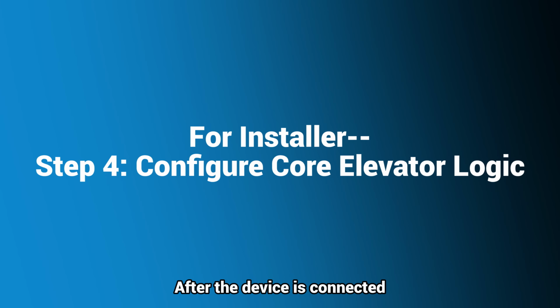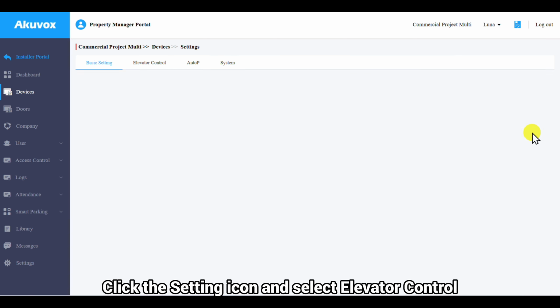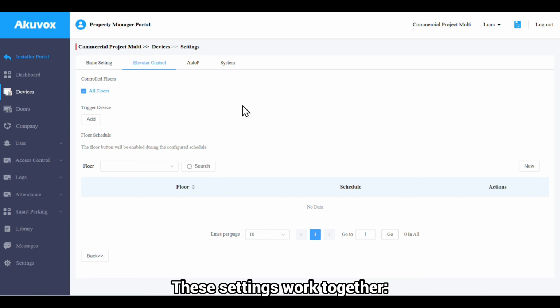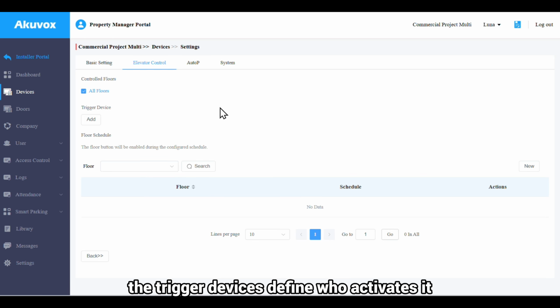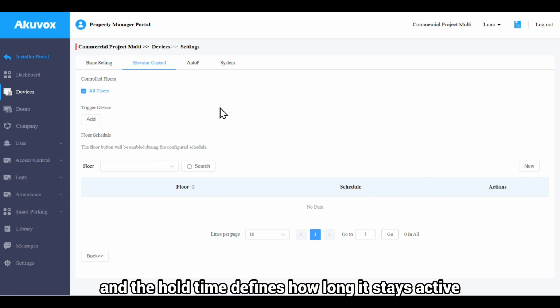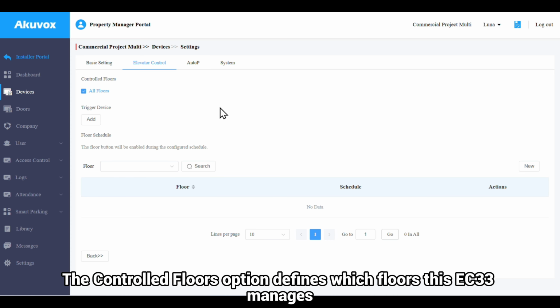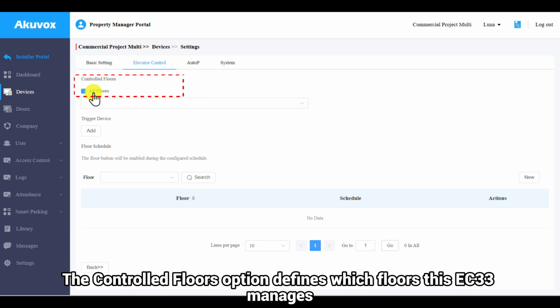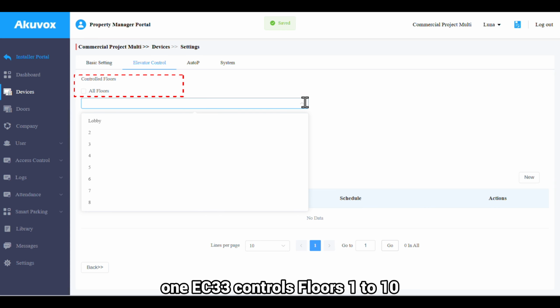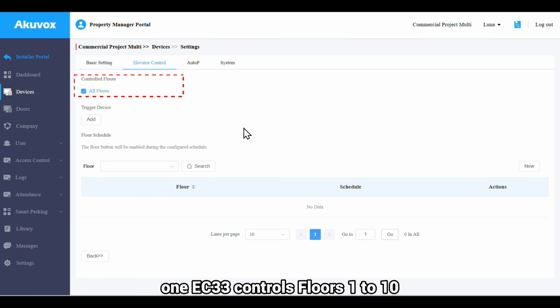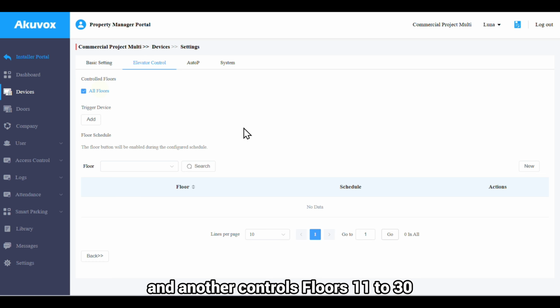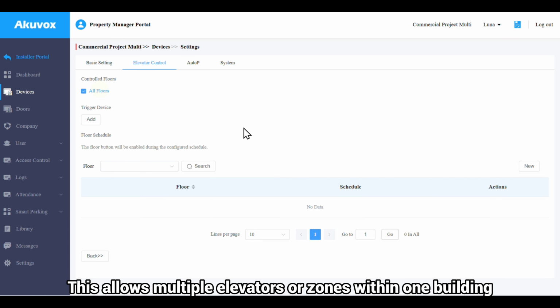After the device is connected, we can define how it behaves. Click the setting icon and select Elevator Control. These settings work together. The floors define the scope, the trigger devices define who activates it, and the hold time defines how long it stays active. The Controlled Floors option defines which floors this EC33 manages. For example, one EC33 controls floors 1 to 10, and another controls floors 11 to 30. This allows multiple elevators or zones within one building.